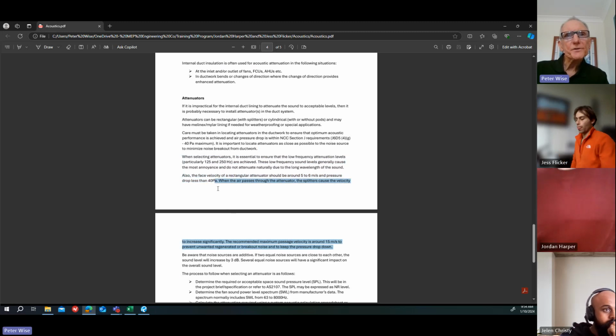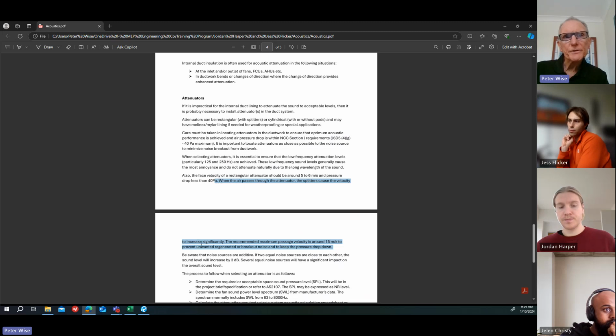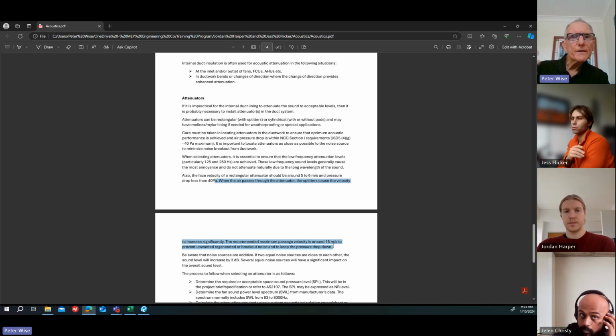So when the air passes through the attenuator, the splitters cause the velocity to increase significantly. The recommended maximum passage velocity is around 15 metres per second to prevent unwanted regenerated or breakout noise and to keep the pressure drop down. As the passage velocity increases through the attenuator, the generated noise will increase as well. And then the attenuator is working against itself in that case, because it's reducing the airborne noise, which is the air going down the ductwork, but it's generating noise through the casing of the attenuator. So be aware of that.